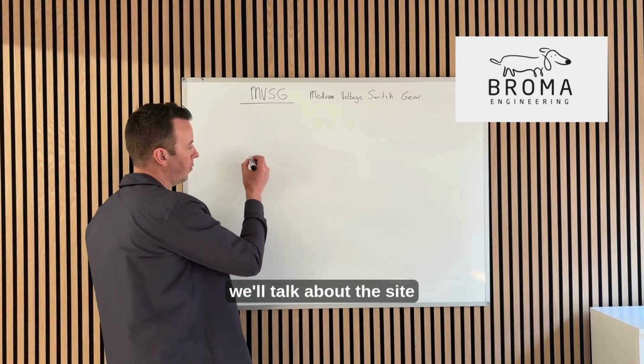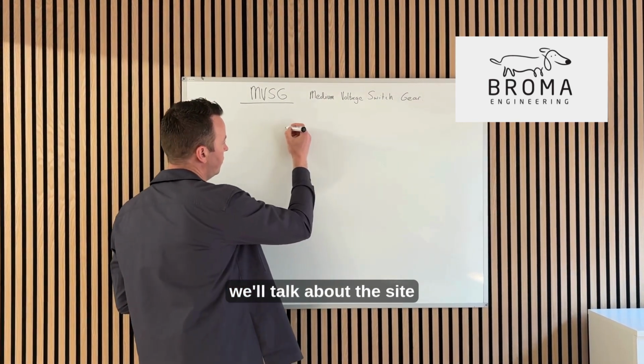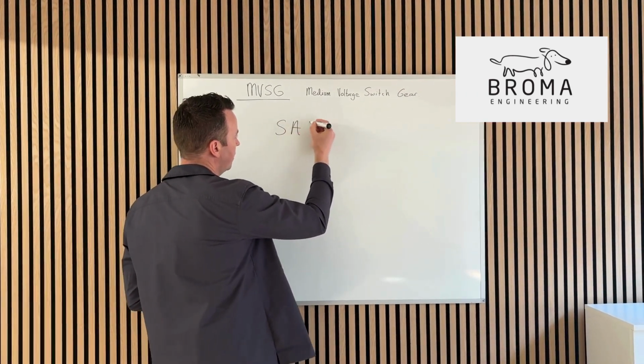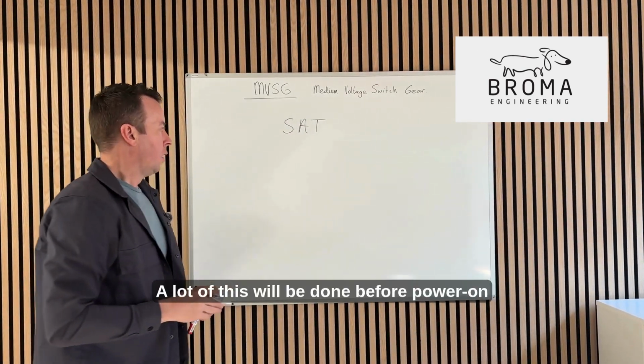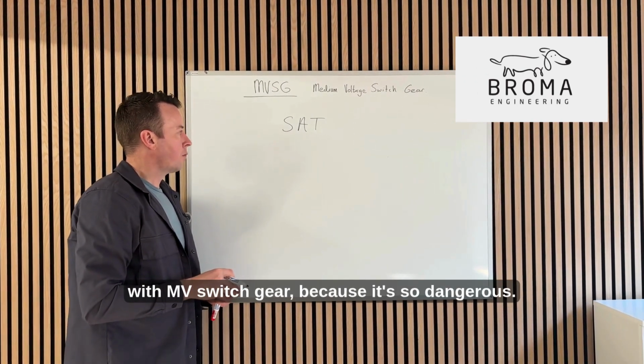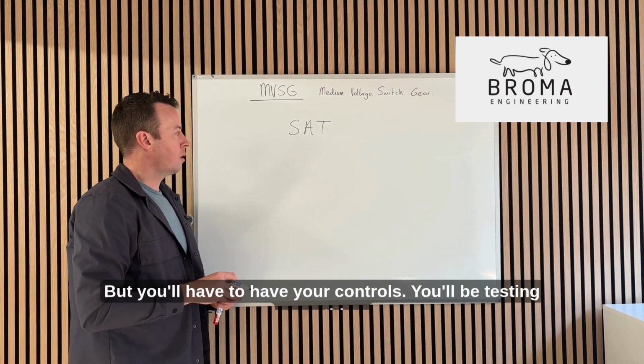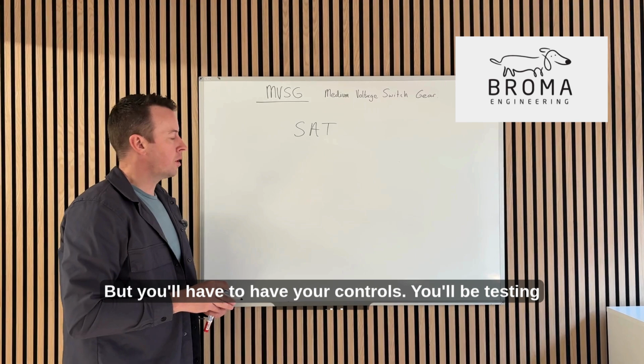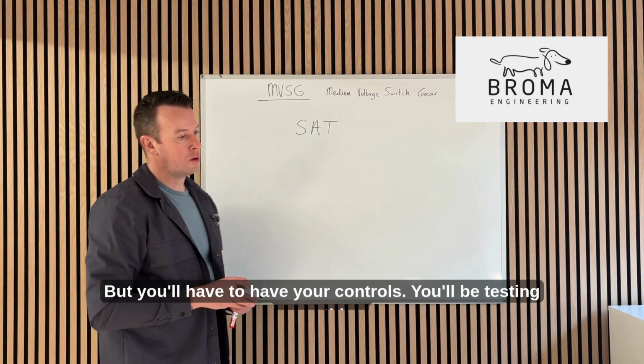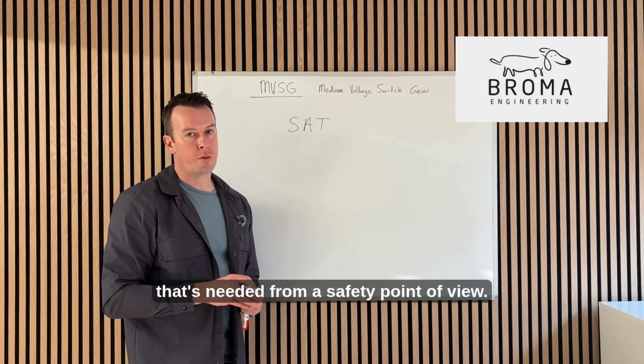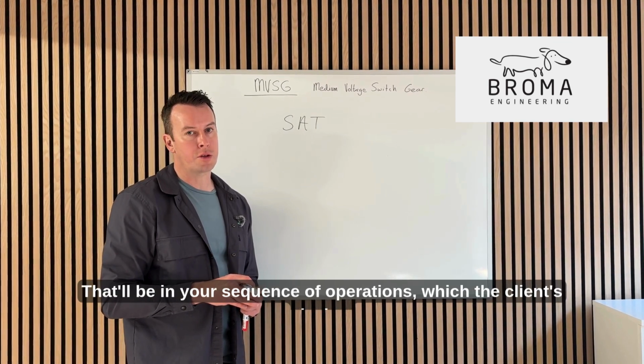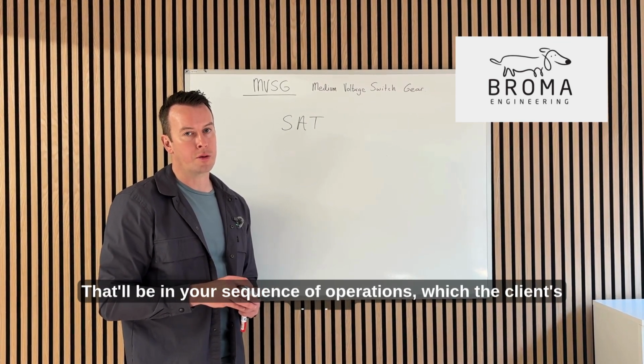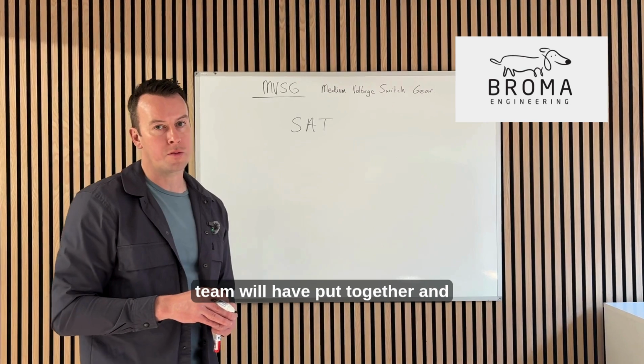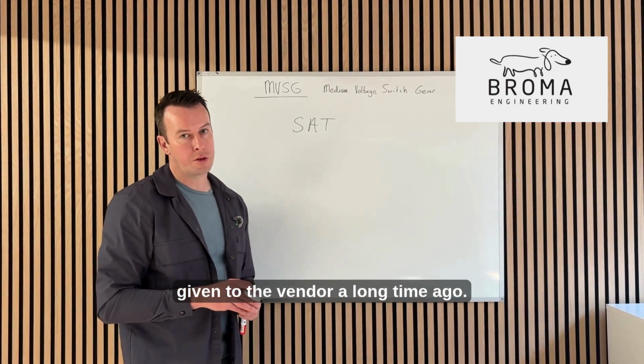We'll talk about the site acceptance testing. A lot of this will be done before power on with MV switchgear because it's so dangerous, but you'll have to have your controls—you'll be testing everything that's needed from a safety point of view. That'll be in your sequence of operations, which the client's design team will have put together and given to the vendor a long time ago.